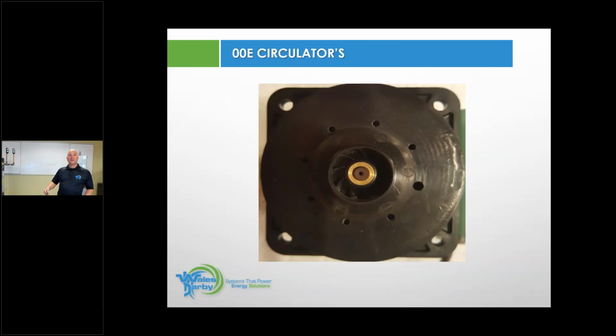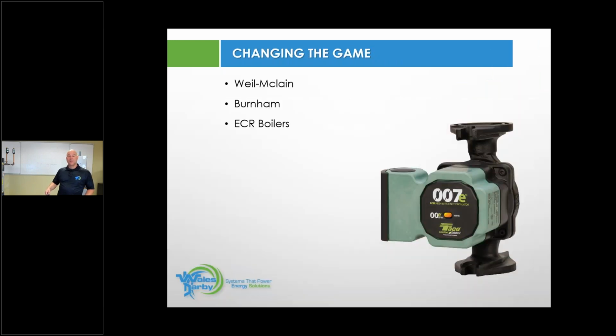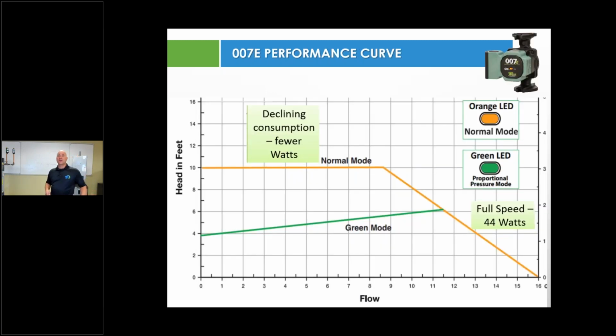Darn it, I hit the wrong one again. There we go. So some of the manufacturers that have made a change to the 007E, you can see them on the screen. So you'll be running across these circulators a little bit more often. And this is the curve of a 007. 10 feet of head, out to about 8.25 gallons of flow, it will stay at 10 feet of head. Once you get beyond 8.25 gallons, it does flow water all the way out to 16 gallons a minute, but that would be at 0 feet of head.